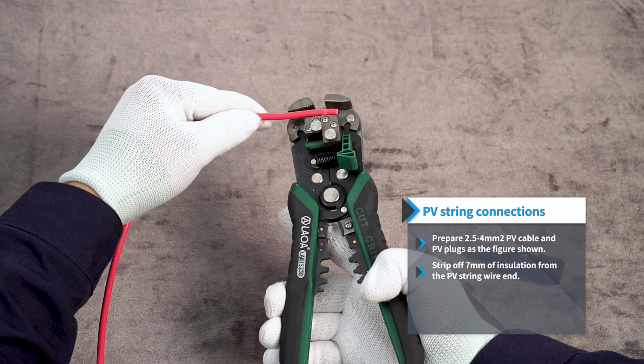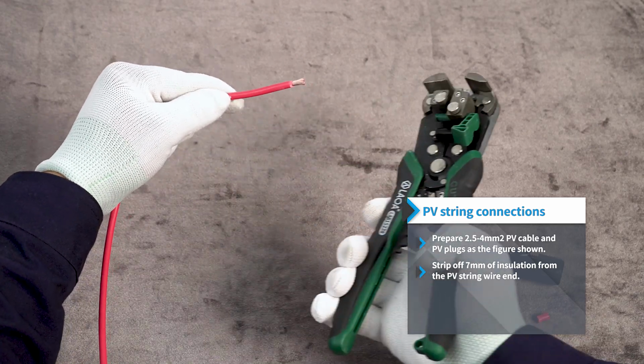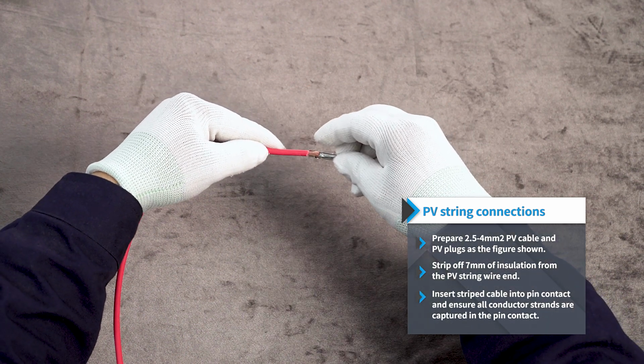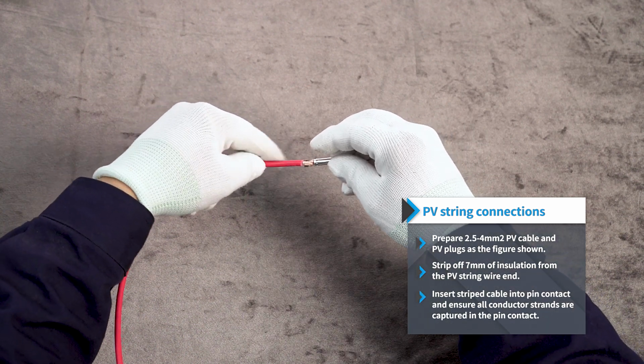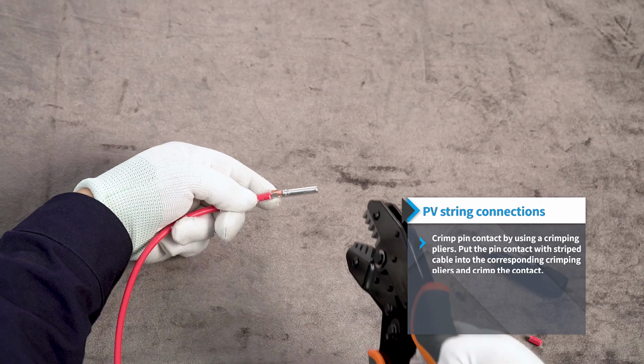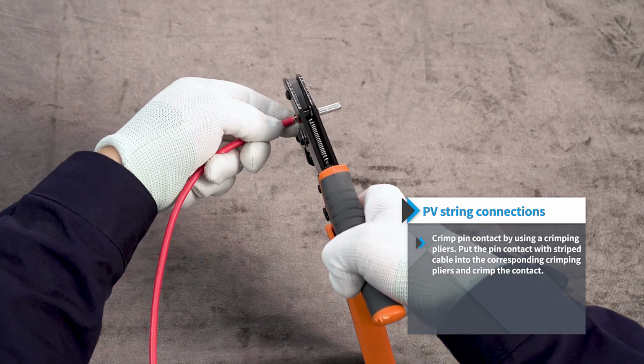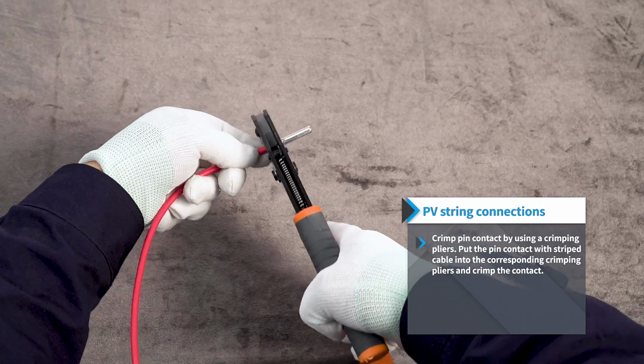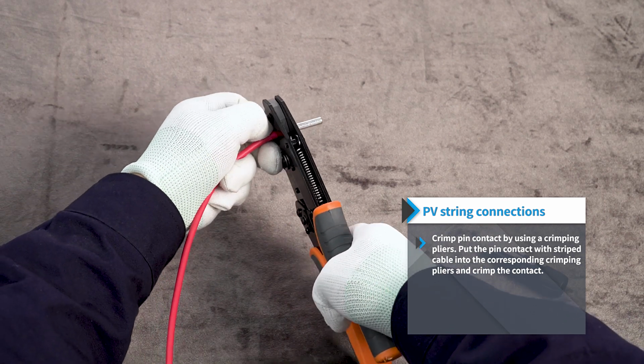Strip off 7 millimeters of insulation from the PV string wire end. Insert stripped cable into pin contact and ensure all conductor strands are captured in the pin contact by using a crimping pliers. Put the pin contact with stripped cable into the corresponding crimping pliers and crimp the contact.